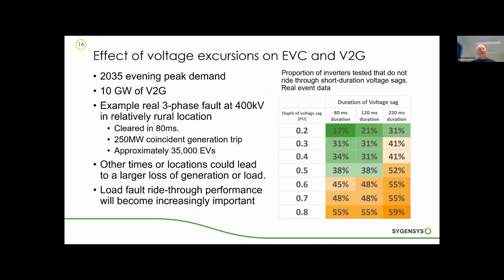If we consider the effect of voltage excursions, within Work Package 2 we took one specific example, which was looking at evening peak in 2035, potentially where we have 10 gigawatts of generation coming from vehicle-to-grid. And we looked at a real-life situation of a 3-phase fault on a 400 kV part of the network in a relatively rural location, actually quite close to our office. That fault was cleared within 80 milliseconds, so a typical fault clearing time.